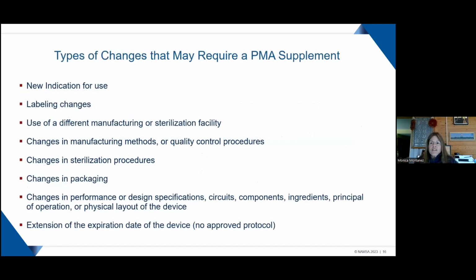So what types of changes qualify for a PMA supplement? Well, of course, new indications for use would be number one. Labeling changes are also included. The use of a different manufacturing or sterilization facility, any changes in your manufacturing methods or quality control procedures, sterilization procedures, changes in packaging, changes in performance or design specifications, extension of expiration date of the device based on data obtained under a new or revised stability or sterility test protocol that has not been approved by FDA. If this protocol has been previously approved by FDA, a supplement is not submitted, but the changes must be reported in your periodic annual reports.